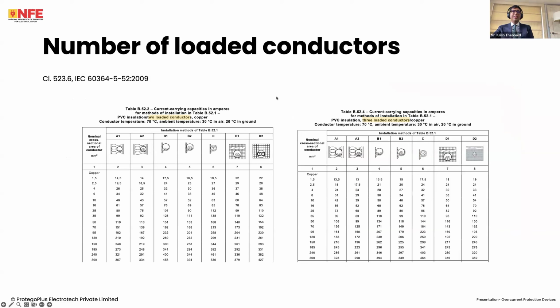Okay, number of loaded conductors, something I want to talk about. This has more to do with harmonics, as we'll address later on as well. And I know some questions have come in about that as well. Current carrying capacity is conventionally defined for a variety of factors, one of them being loaded conductors. What this means is that for a single phase circuit, we're only considering line and neutral conductors being loaded. For a three phase circuit, we're only considering L1, L2, L3, or RYB as being loaded. In this case, if there is an unbalanced three-phase circuit and there's a current in the neutral, we need to take that into account. Deviation has to be applied because these values only apply for three loaded conductors. If you're in effect having four loaded conductors, that affects your ability of the cable to dissipate heat.